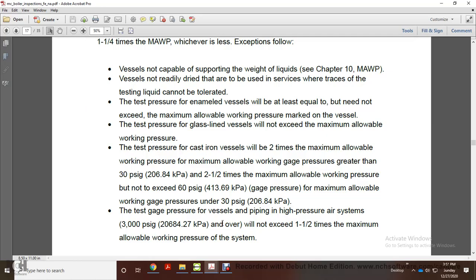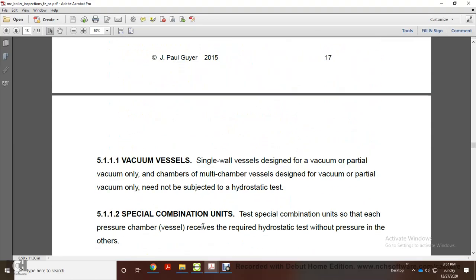The test pressure of cast iron vessels will be 2 times the maximum allowable working pressure. For a maximum allowable working gauge pressure greater than 30 psi gauge, 2.5 times the maximum allowable working pressure, but not to exceed 60 psi gauge for maximum allowable working pressures under 30 psi gauge. The test pressure for the vessel piping of high pressure air systems will be 1.5 times the maximum allowable working pressure of the system.